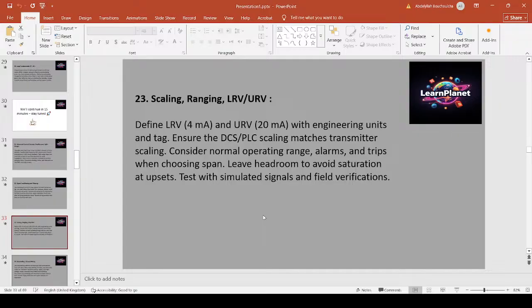Scaling, ranging, LRV, URV. Define LRV 4 mA and URV 20 mA with engineering units and tolerances. Ensure the DCS and PLC scaling matches transmitter scaling. Consider normal operating range, alarms, and trips when choosing span. Leave headroom to avoid saturation at upsets. Test with simulated signals and field verification.